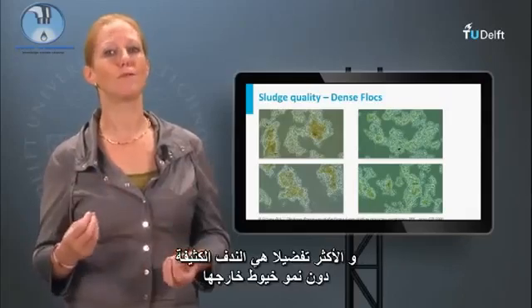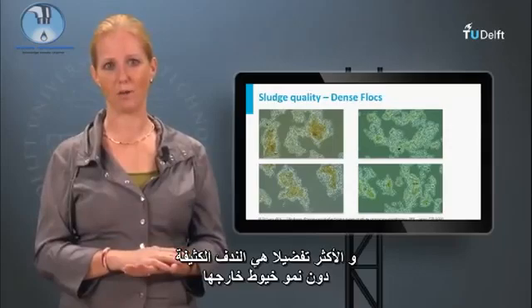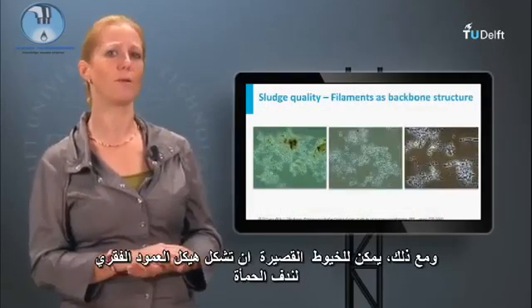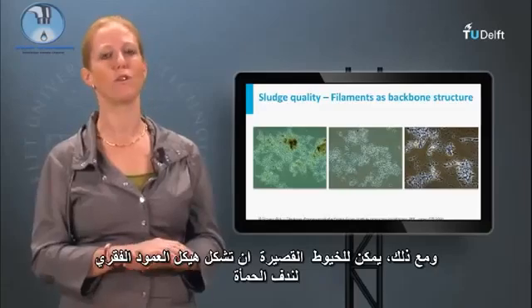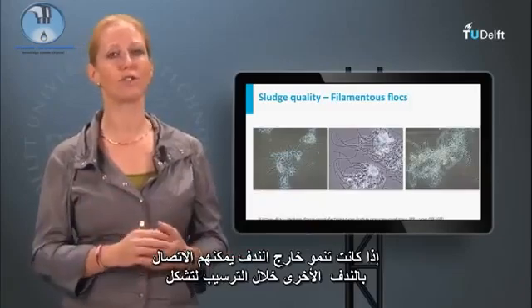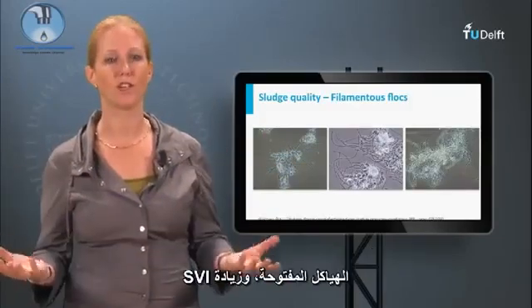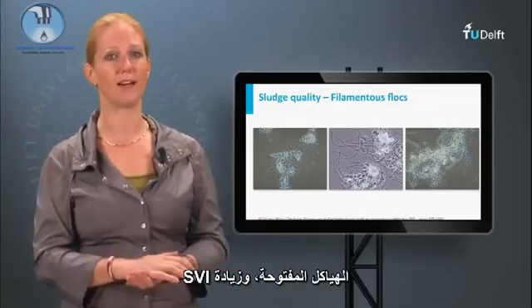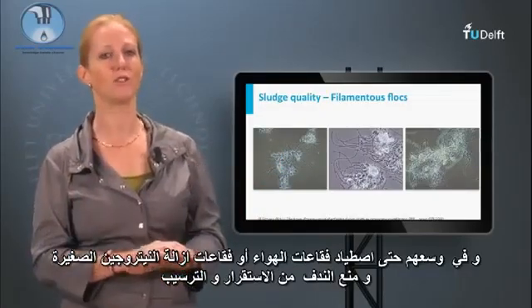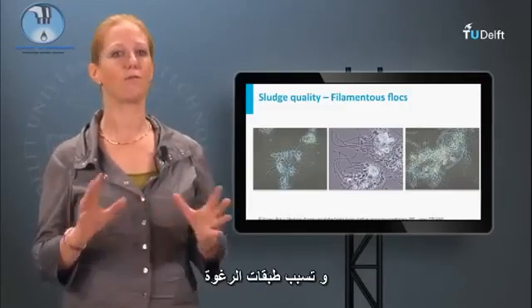What is most preferred are nice and dense flocs without filamentous outgrowth. However, short filaments can form the backbone structure of sludge flocs. If they grow outside the flocs, they can bridge to other flocs during settling, forming very open structures and increasing the SVI. They can even trap small air or de-nitrogen bubbles, preventing flocs from settling and causing foam layers.